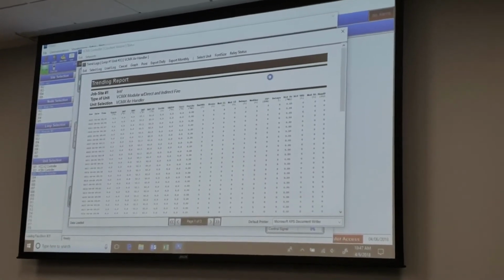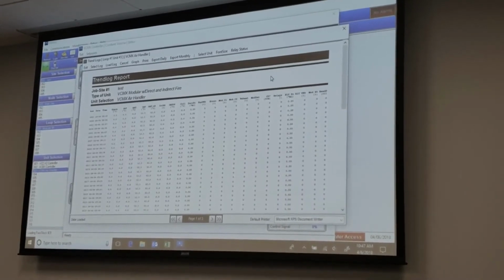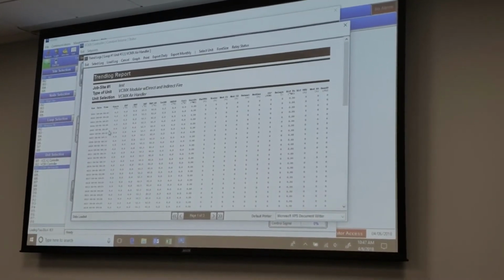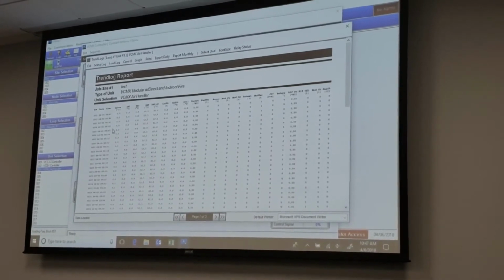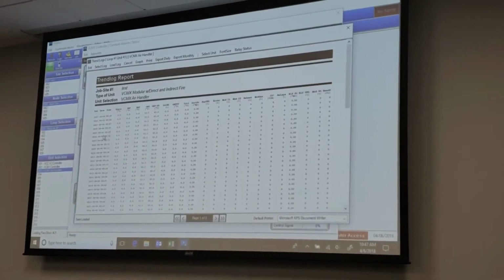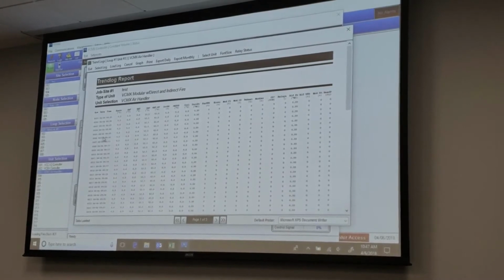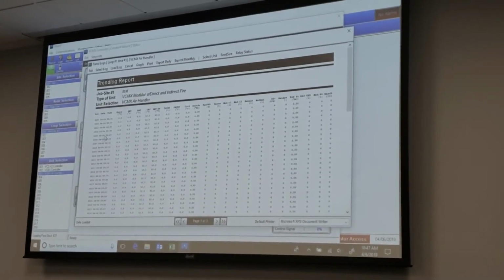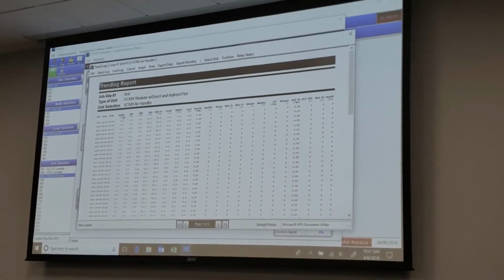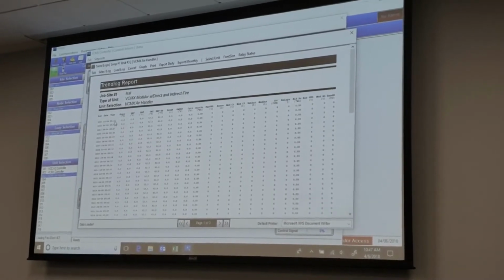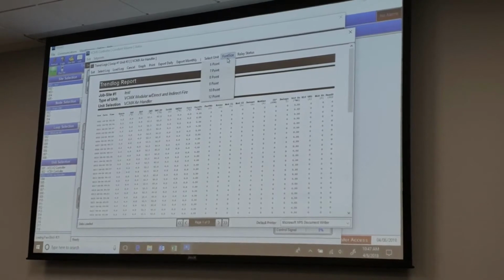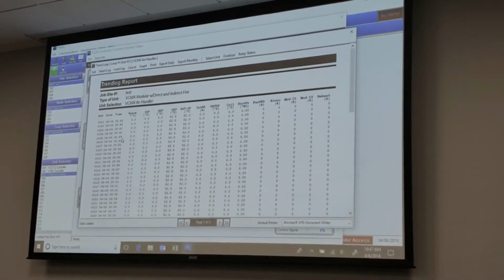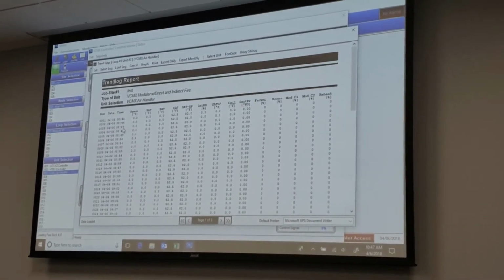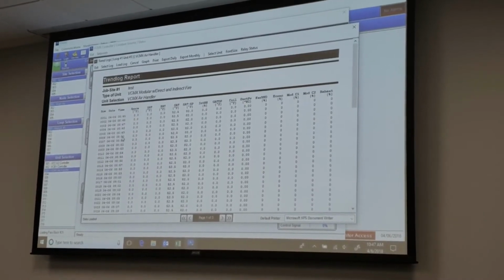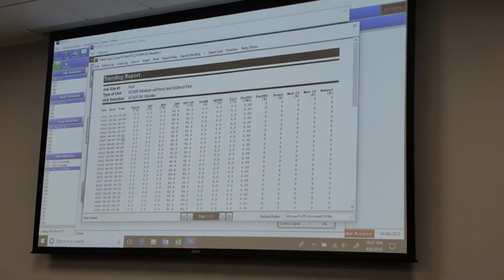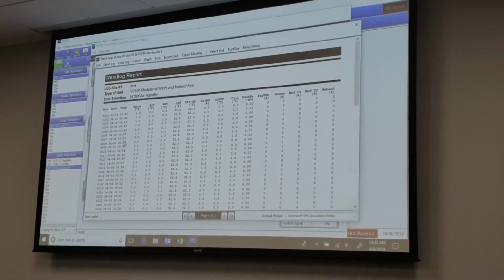Power up counts were within reason, but the guy was saying, "No, I only shut it down for 2 or 3 minutes and brought it back up." And it turned out he was shutting it down through lunch, 45 minutes, an hour. And they said, "No, he didn't have it shut down that long." And I said, "Well, here it is right here, guys, time and date stamped." We're going to make the font size a little bigger so we can see it. All right, time and date stamp here. And we went all the way down to 850, and then it jumped to 905.